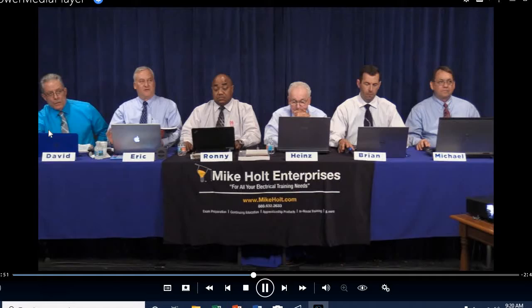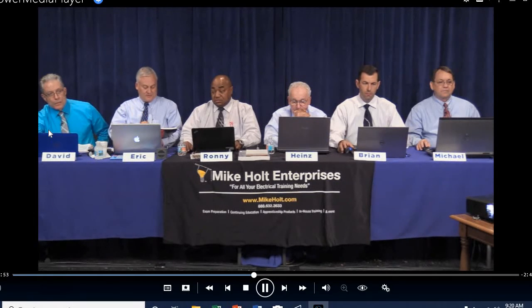Eric? Yeah, Mike, you didn't cover this, but it brings up a good point. The article for 408.3(E)(1) is AC phase arrangement, and it talks about alternating current phase arrangement on three-phase buses shall be ABC from front to back, top to bottom, or left to right. The only reason I bring this up is that I've had inspectors read this thinking that, for example, the conductors terminating on a breaker should be ABC left to right.